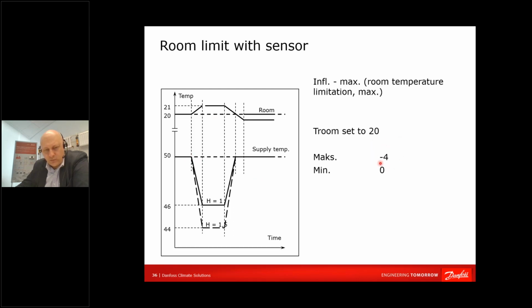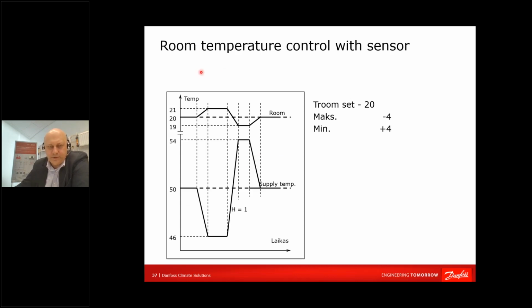For example, if we have setting -4 as the maximum influence factor, your reference or supply temperature, depending on the heat curve value, will be decreased. For example, if we have heat curve equals 1, then supply temperature will be reduced 1 times -4 up to 46 degrees, and after your room temperature will decrease, then temperature will be returned to the previous value. So you see the limit is just working as limiter. If you would like to operate as a reference room controller, you have to enter 2 digits, minus, plus. So reference temperature will be adjusted accordingly to the fluctuation of the room temperature.